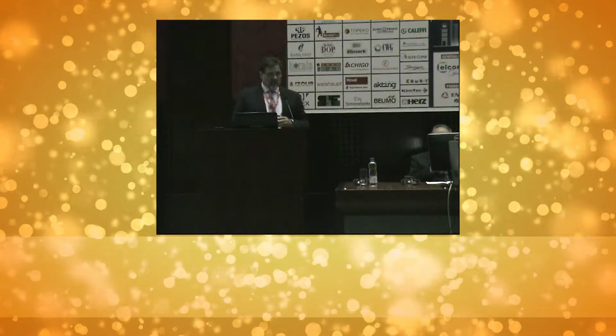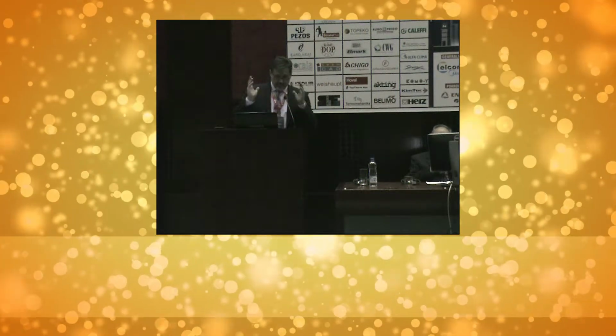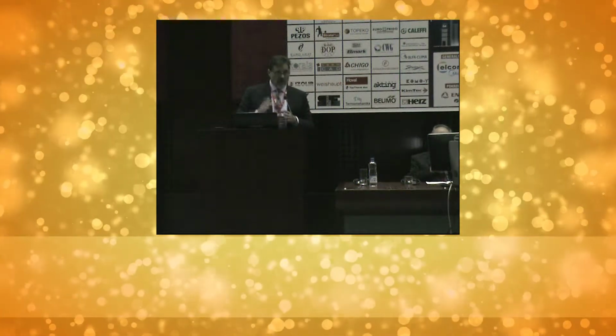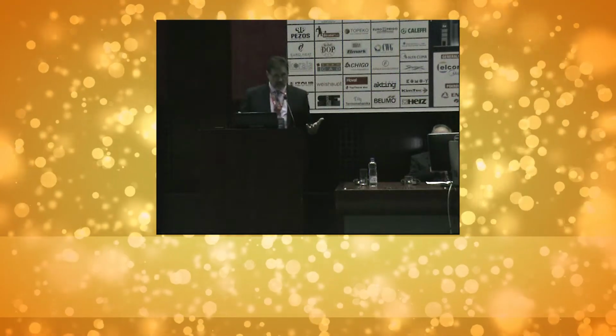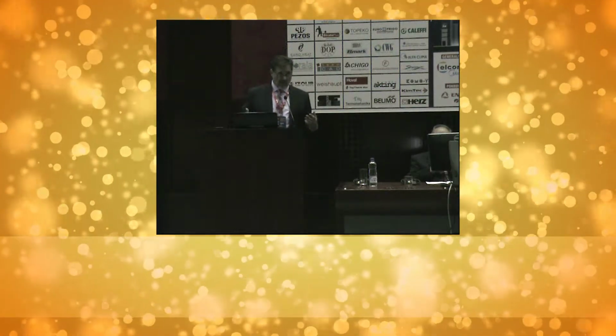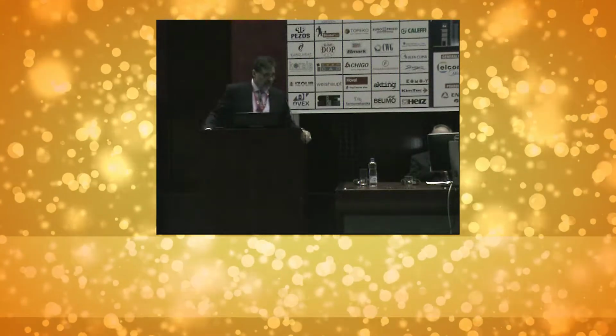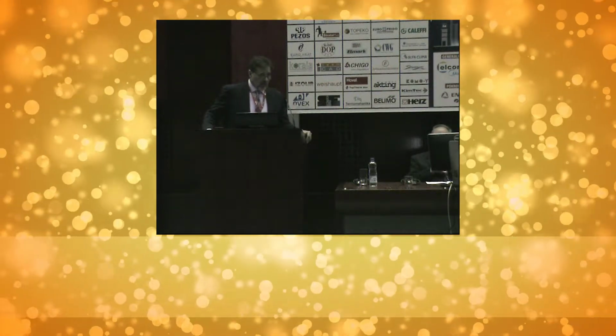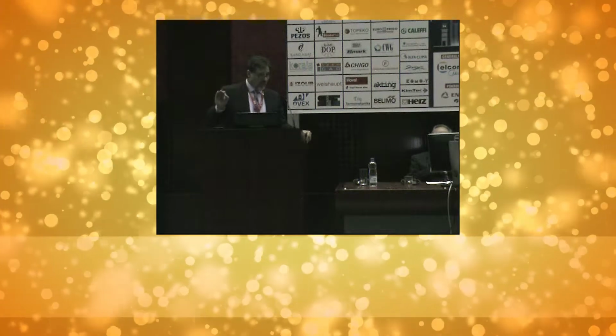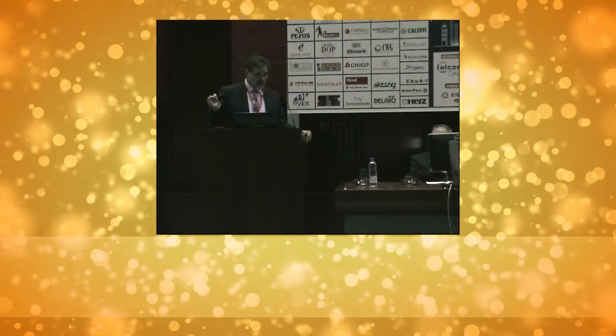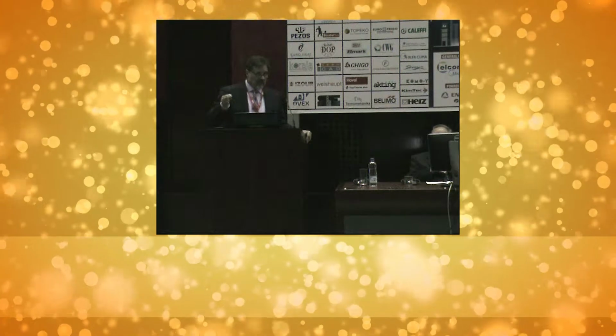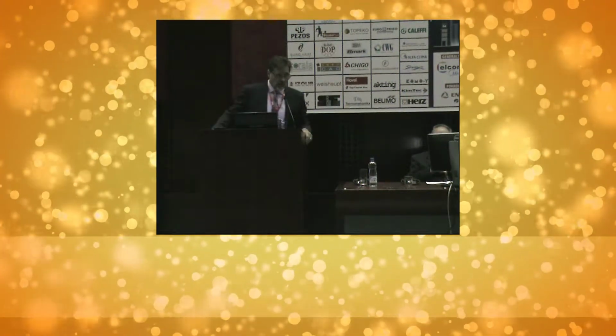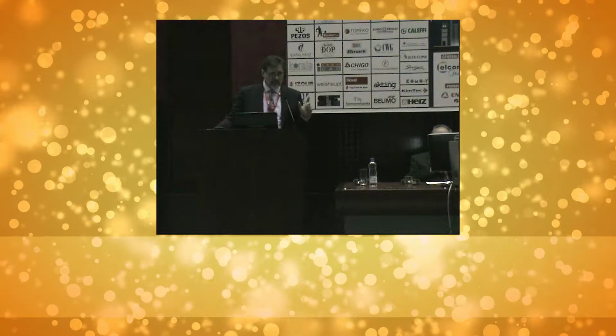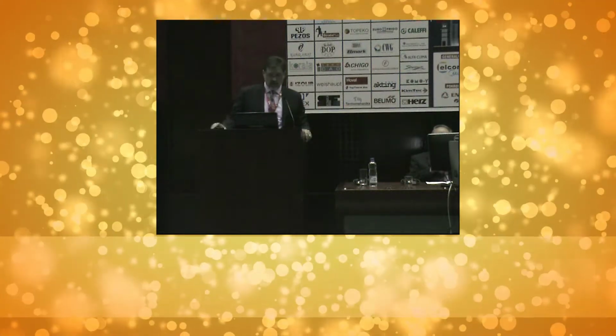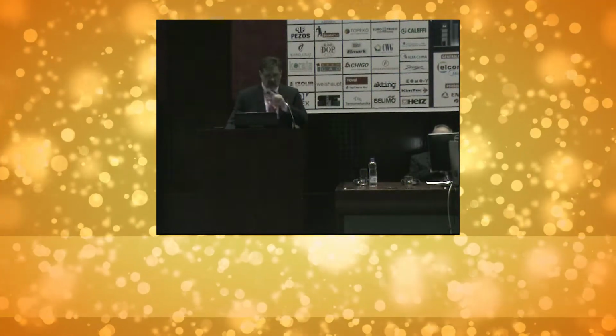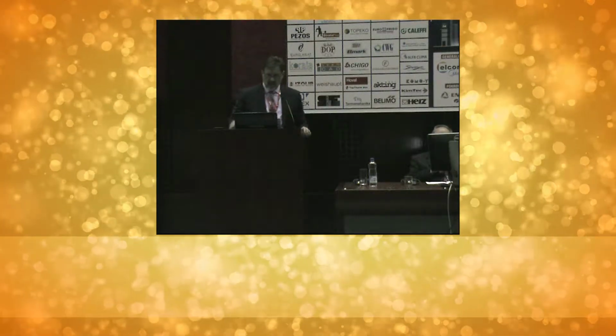So when we said work on, we said this is how much CFM we're going to bring, and when we said work off, that's where the tremendous energy savings come from. Remember, you have to bring the 55 degree air no matter what. If you're in unoccupied mode and you bring 400 feet per minute, which is 160 CFM, you have to reheat that 160 CFM to 90 in most of the unoccupied modes. That is a third. That's where the payback comes back to 1 year. You can study this and figure out how we did that.